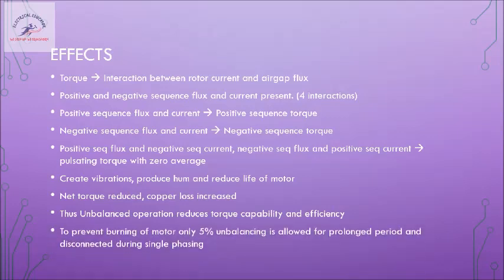To prevent the burning of the motor, we allow only 5% of unbalance, because in the beginning of the slide we said that sometimes we intentionally unbalance the supply voltage to control the speed in drives. So there also only 5% of unbalancing is allowed, that is for a prolonged period, and for a shorter duration we can unbalance it to any extent. Okay, and as soon as single phasing occurs, the motor is disconnected from the supply unless it is very lightly loaded. So these are the concepts which we had to discuss.